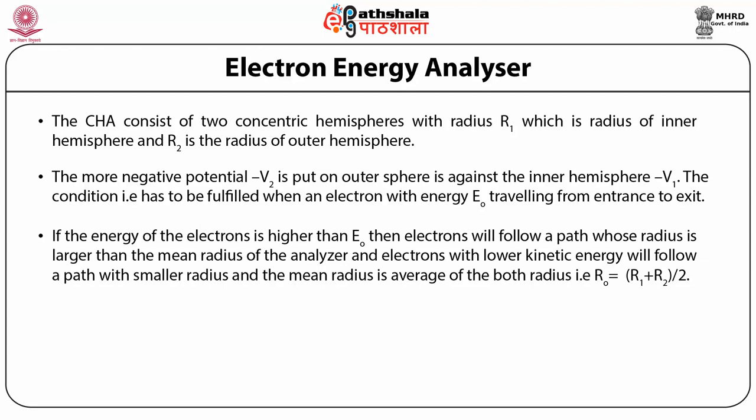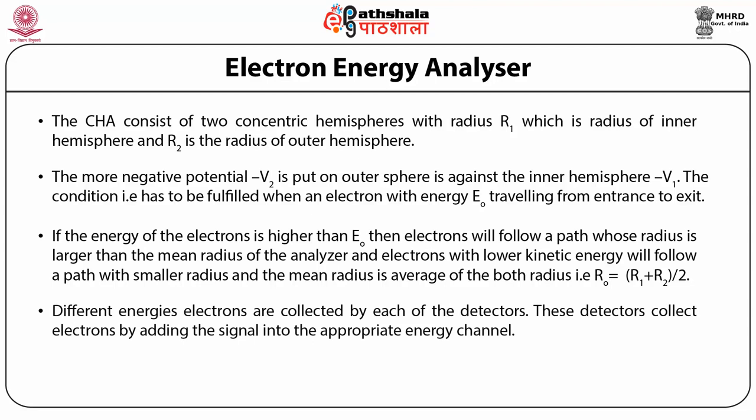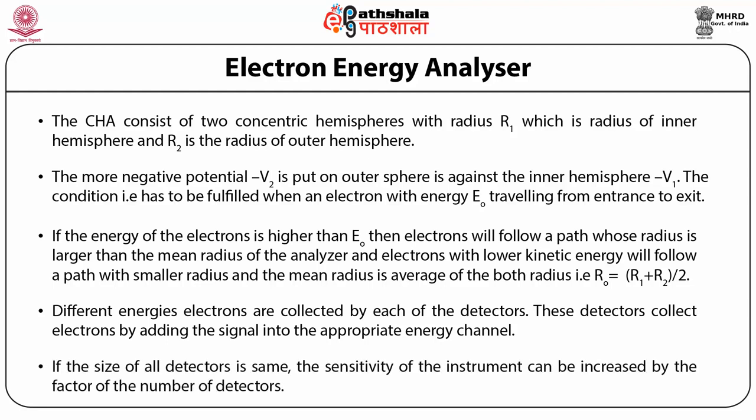If the energy of the electron is higher than E0, electrons will follow a path whose radius is larger than the mean radius of the analyzer. Electrons with lower kinetic energy will follow a path with a smaller radius. At the output plane, a number of detectors are provided. Different energy electrons are collected by each detector, adding the signal into the appropriate energy channel. If the size of all detectors is the same, the sensitivity of the instrument can be increased by a factor equal to the number of detectors.